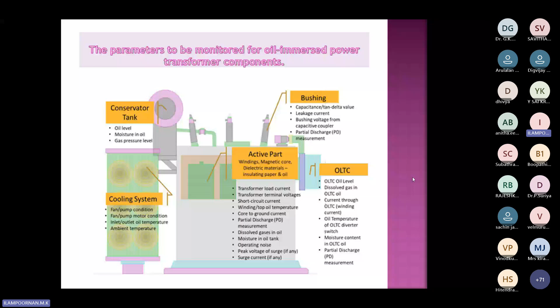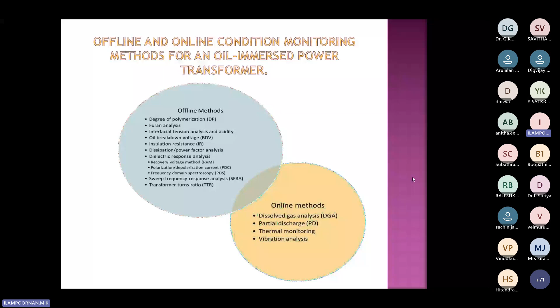So this we have already dealt in detail. We'll move on. First, what are the two insulations which we are going to deal with in the transformer? One is insulation paper, another one is oil. This is like a beautiful combination which has actually sustained for almost 150 years. So why is this combination taking place? Why do we have a paper-oil system? Many people have tried many things like varnish, mica based insulation, sealed transformers, in fact solid transformers. People have tried a lot to change this combination, but still, even after 150 years, the solid standing is there between the oil and the paper.